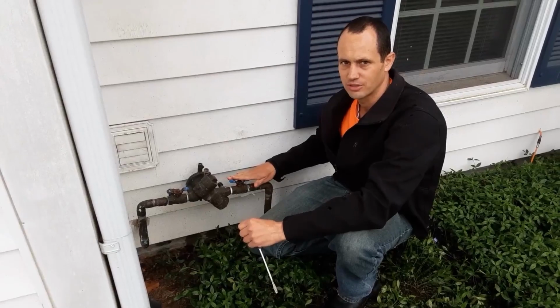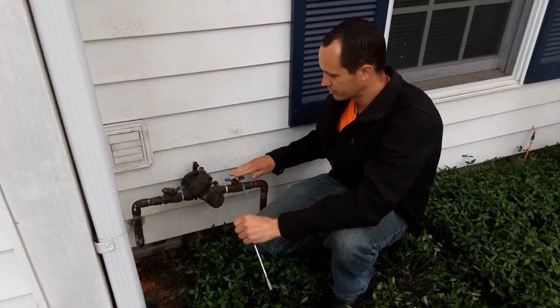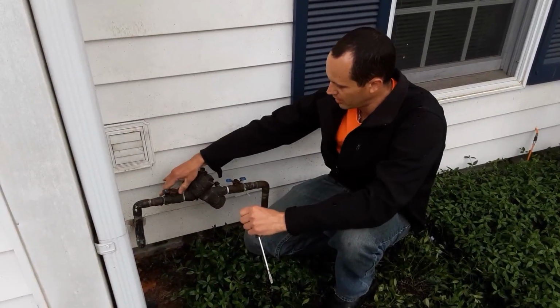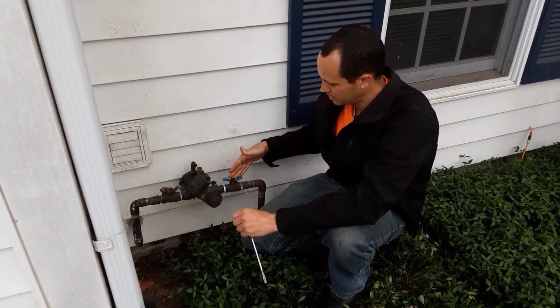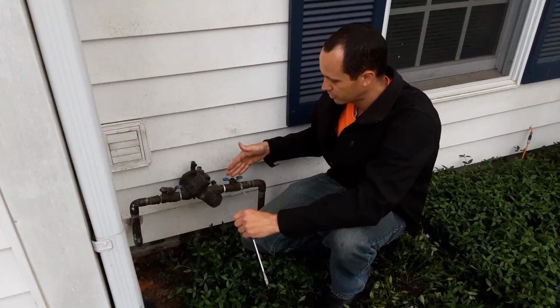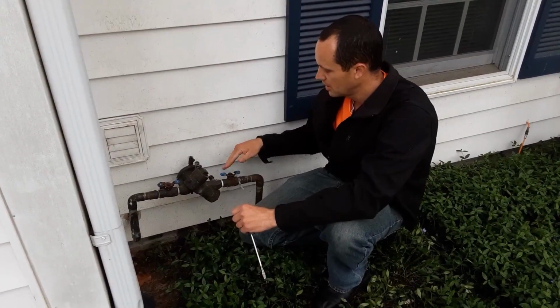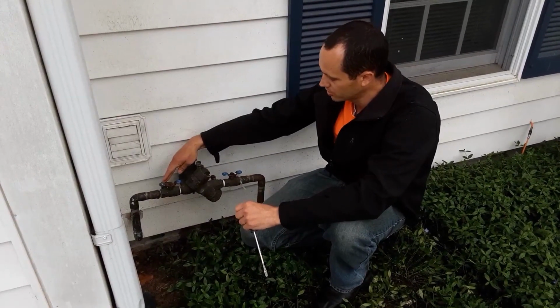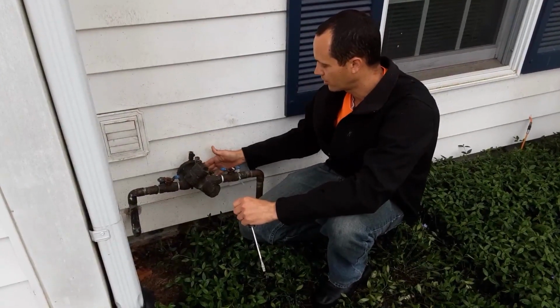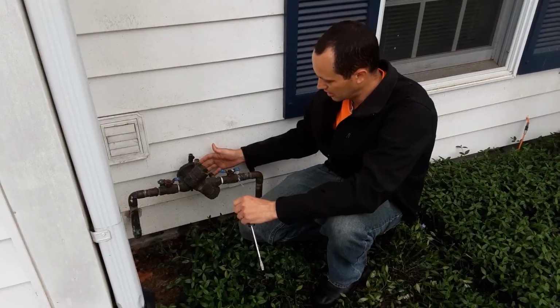Alright, so now the sound has stopped. There's no more water flowing through this valve, so I'm just going to make sure that all the valves on this main line, these two valves rather, are open so that the water can flow to the sprinkler system. And I want to make sure that none of these test ports are leaking and that no other part of the backflow prevention device is leaking.